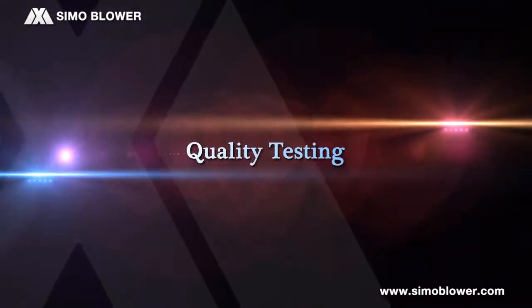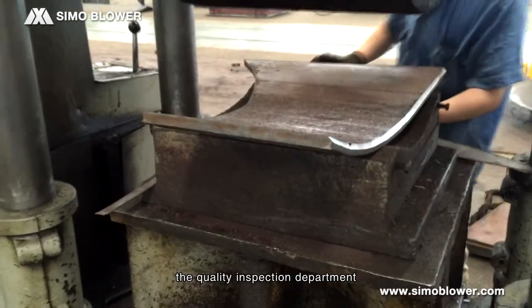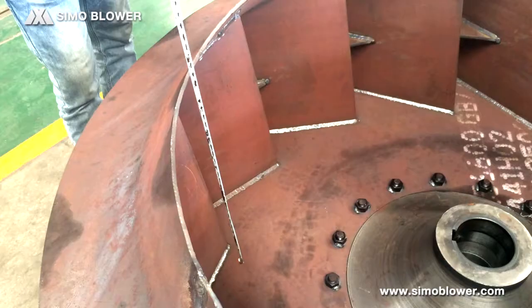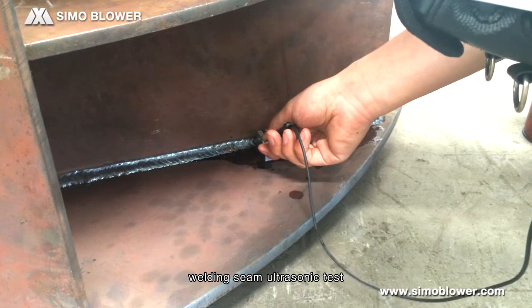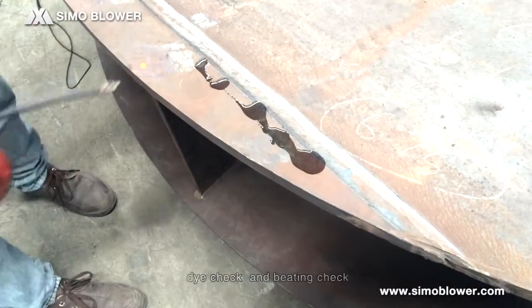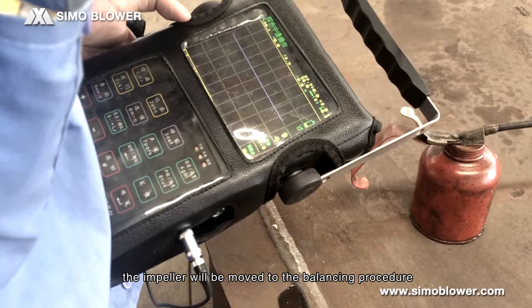Quality Testing. After stress relief, the quality inspection department performs shape line inspection, size check, welding seam height test, welding seam ultrasonic test, dye check, and beating check. After passing all inspections, the impeller is moved to the balancing procedure.